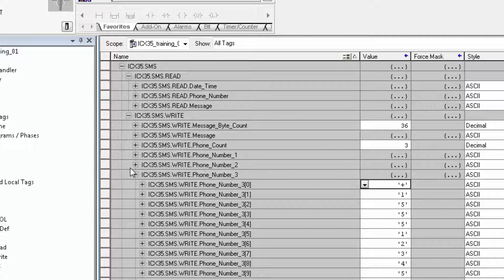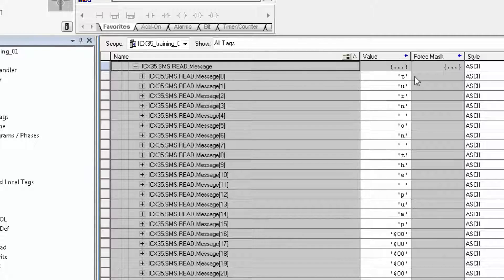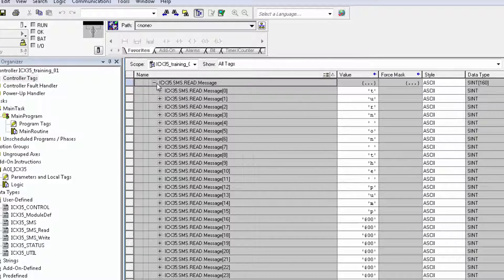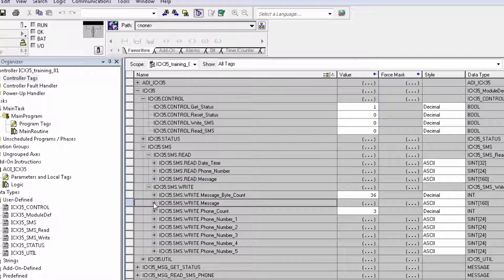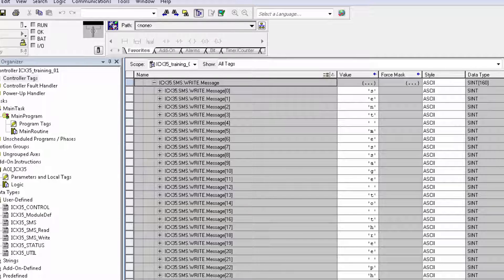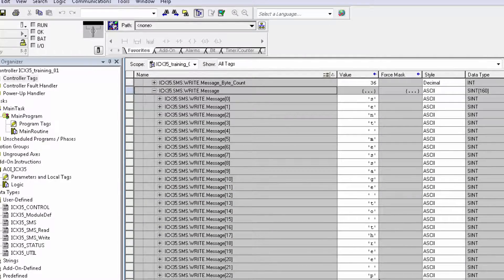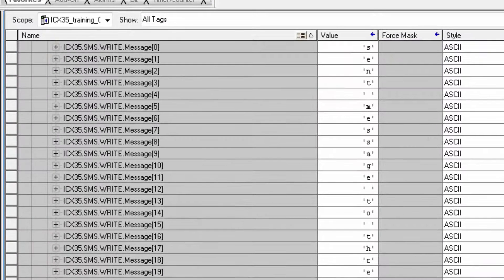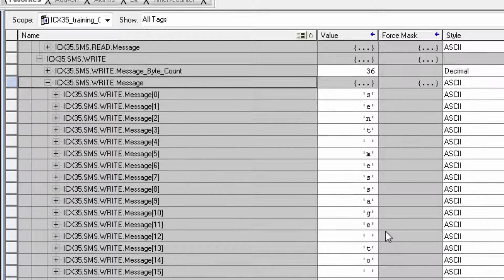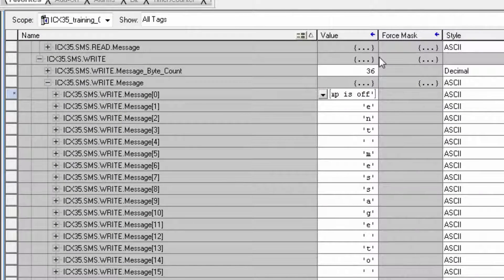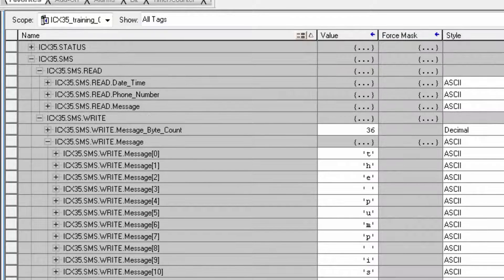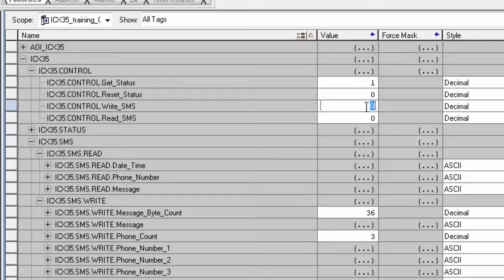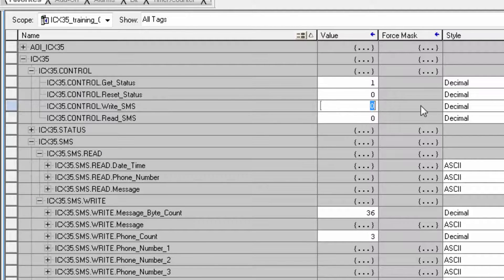If we look under a read message, we can see the actual text message being read from the ICX35. Looking under the SMS write array, we see everything works the same with the phone numbers. Under write message, you can enter in a message that can be sent out as an SMS text to all the numbers in the phone number tags. As with entering the phone numbers, you can just type in your message in the first tag and hit enter and RSLogix will format it into the tags. To trigger this SMS write, you can go to the controller tag, like you would for all the other commands, and toggle the ICX35 control dot write SMS tag.